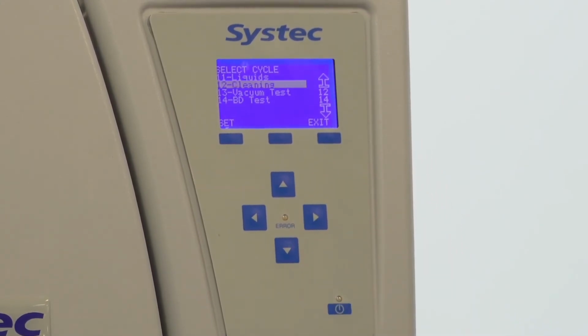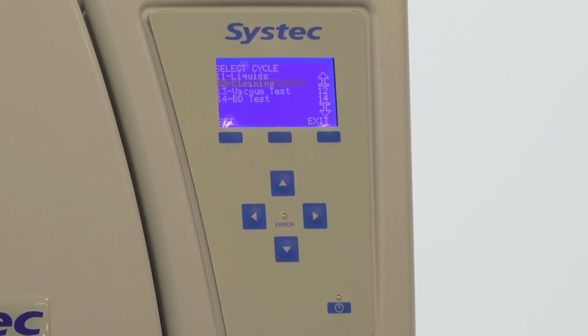We do have an automated cleaning cycle inside of all of our units that we recommend running weekly or bi-weekly, depending upon how much use the instrument is going to get. It is pre-programmed. It goes to a higher temperature and pressure than any of the other cycles that we have. The other cycles are more process driven, whereas this is driven to not only clean the autoclave, but flush any of the valves inside of the unit.